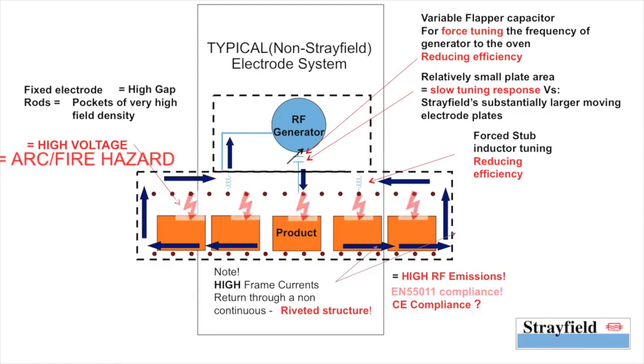Now, given the high frame currents and the high RF emissions resulting from these frame currents, this system has physically no chance of complying with the EU legislation for RFI and EMI, that is radio frequency interference and electromagnetic interference. So what chance, if any, does it have of being compliant with CE marking?